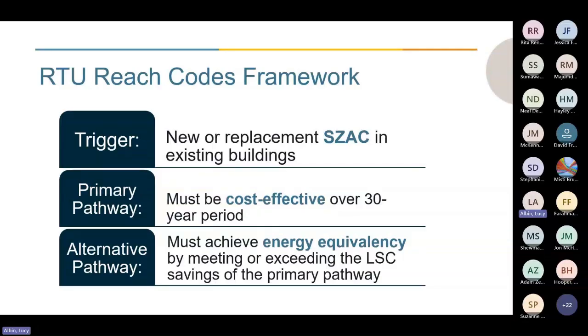First, the trigger for when this reach code would apply would be a new or replacement single zone AC RTU in existing buildings. For each reach code option, we have two prescriptive pathways. The first must be cost effective over the 30-year period, as Shannon described those metrics just now. The second alternative pathway must achieve energy equivalency by meeting or exceeding the LSC savings of the primary pathway. Generally the heat pump package would be the first pathway, so that would have to be cost effective, and the single zone AC alternative approach for compliance would have to meet or exceed that energy equivalency.